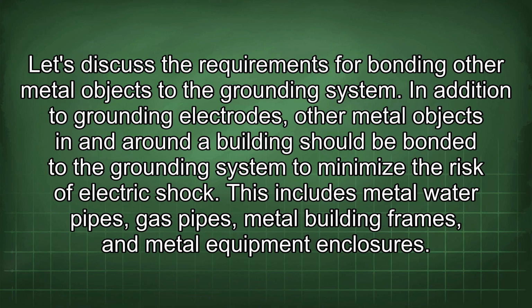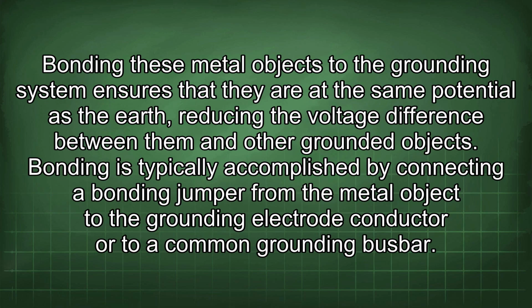Let's discuss the requirements for bonding other metal objects to the grounding system. In addition to grounding electrodes, other metal objects in and around a building should be bonded to the grounding system to minimize the risk of electric shock. This includes metal water pipes, gas pipes, metal building frames, and metal equipment enclosures. Bonding these metal objects to the grounding system ensures that they are at the same potential as the earth, reducing the voltage difference between them and other grounded objects.